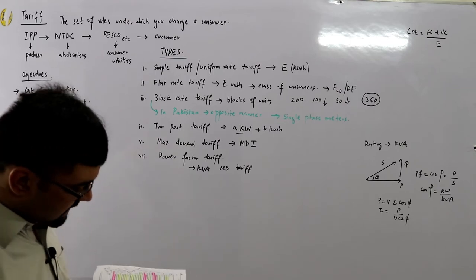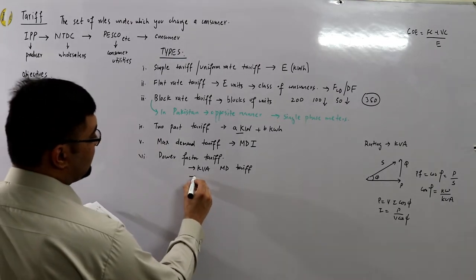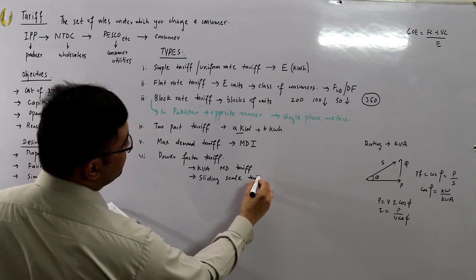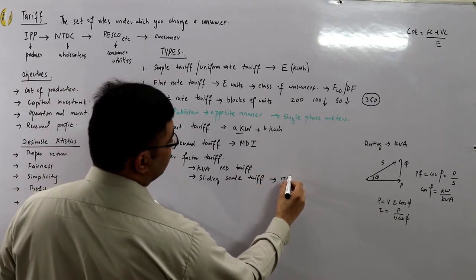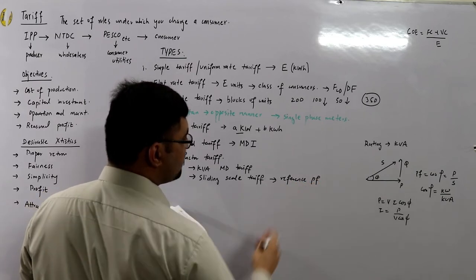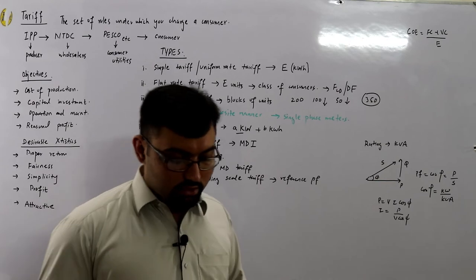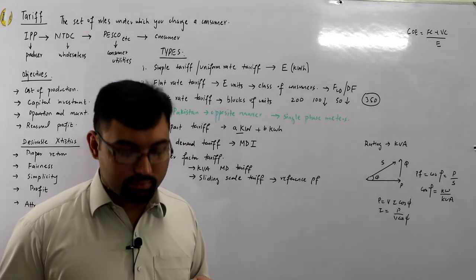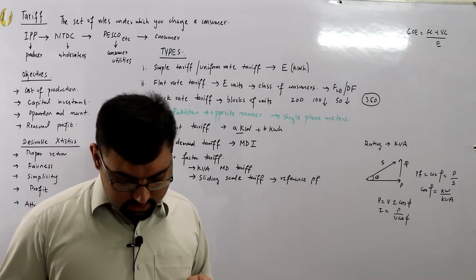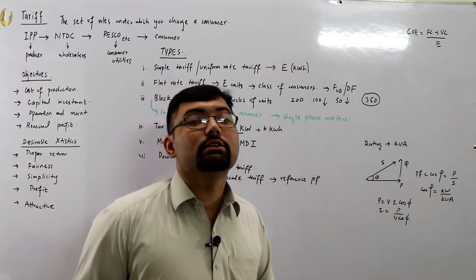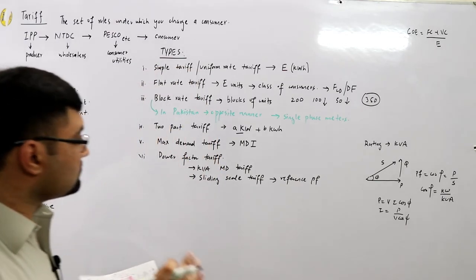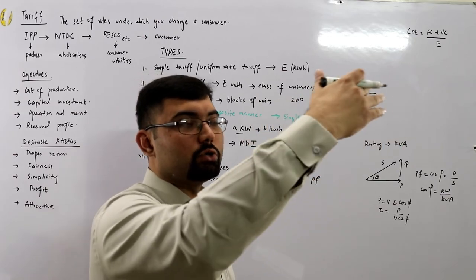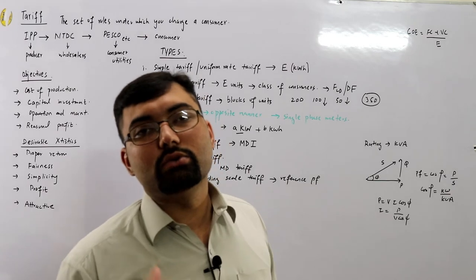Yes. Now the next is the sliding scale tariff. In a sliding scale tariff, you set a reference value of the power factor, and then you do things based on that. For instance, you take the average power factor. This is also called the average power factor tariff. So you take a reference power factor. If a consumer falls below that power factor, you charge him extra.